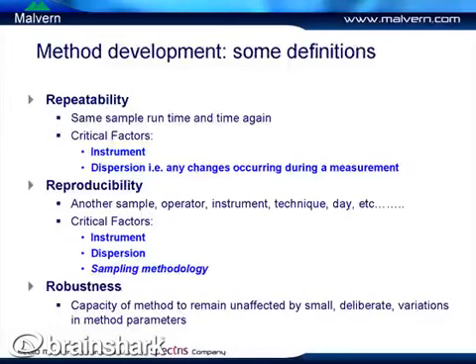Before going through the process of method development, we need to look at the parameters on which the guidance is based. First is repeatability of the measurement. This is determined from repeated measurements of the same sample — the same aliquot or subsample — measured a number of times, testing the instrument and the state of dispersion. From the repeatability test, we can see whether the sample is in a stable state of dispersion, whether it's agglomerating or dissolving, or changing with time in other ways.